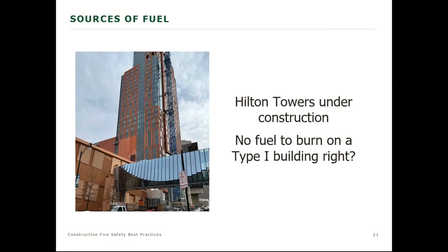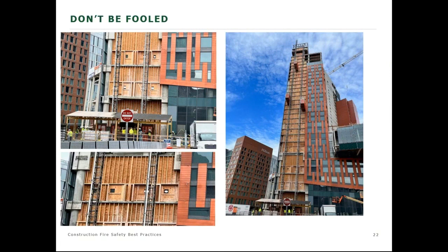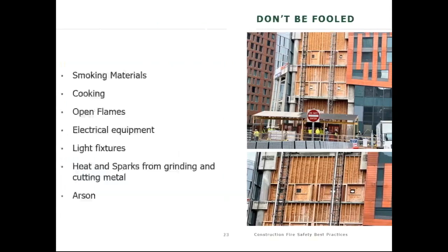So don't be fooled just because it's a type 1 building under construction. Even concrete cast-in-place construction uses wooden forms. Type 1 and type 2 buildings still have combustible contents - vinyl tub kits, packaging. They still have hazmats and flammable combustible gases. So don't be fooled by the type of building that's being constructed. They had a fire actually in Brooklyn a couple years ago, a concrete building under construction, that went to 6 alarms.